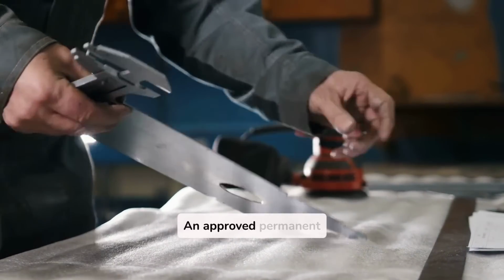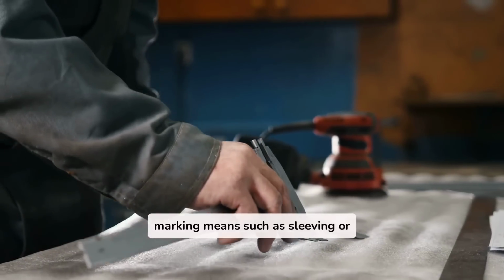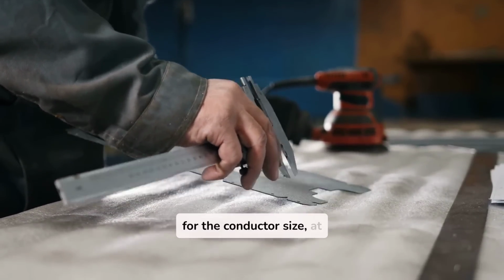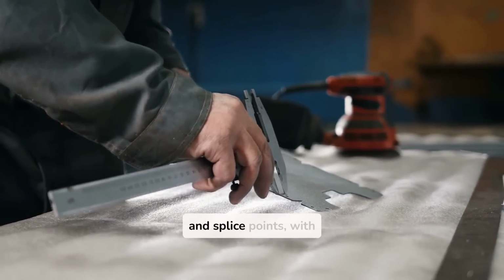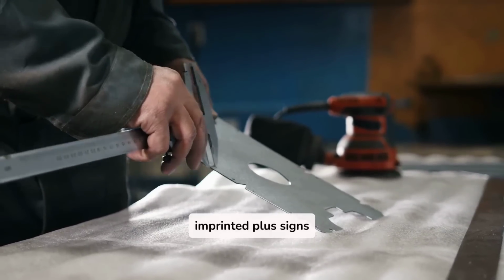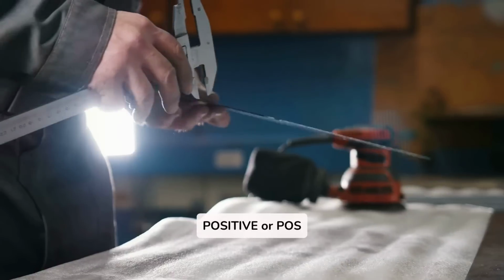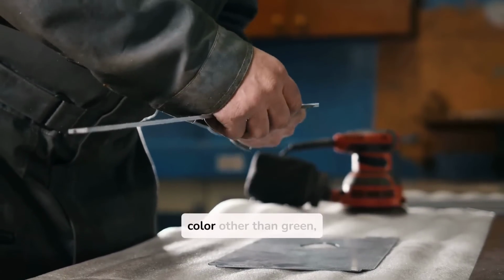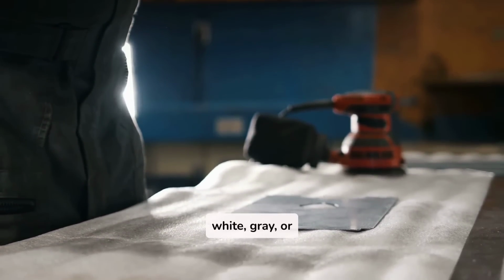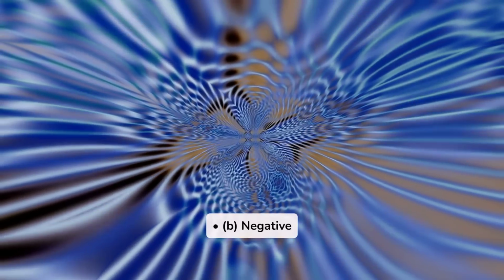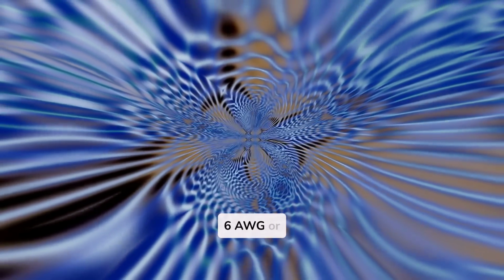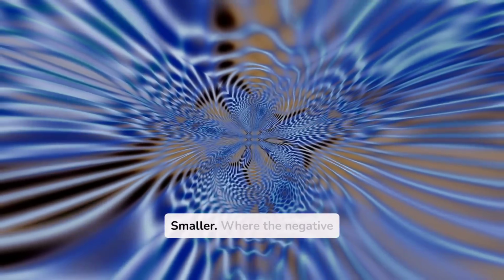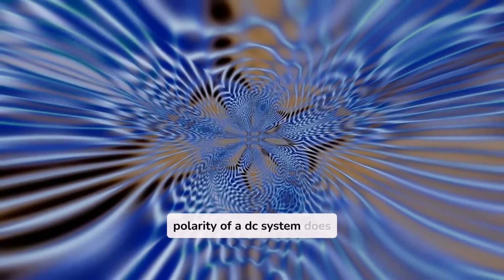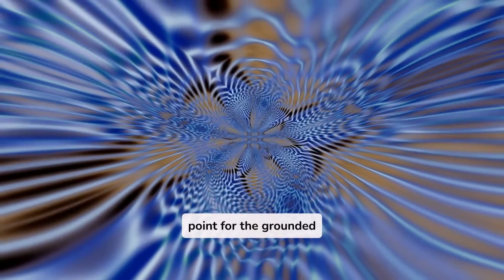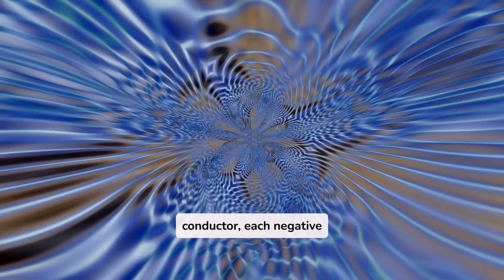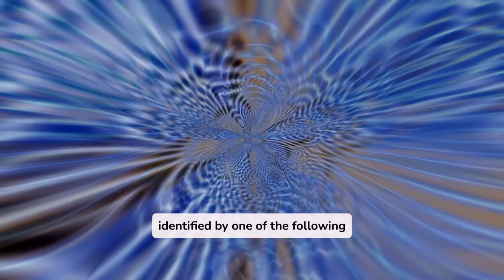4. An approved permanent marking means such as sleeving or shrink tubing that is suitable for the conductor size at all termination, connection, and splice points with imprinted plus signs (+), or the word positive or POS durably marked on insulation of a color other than green, white, gray, or black. B. Negative polarity, sizes 6 AWG or smaller. Where the negative polarity of a DC system does not serve as the connection point for the grounded conductor, each negative ungrounded conductor shall be identified by one of the following means.